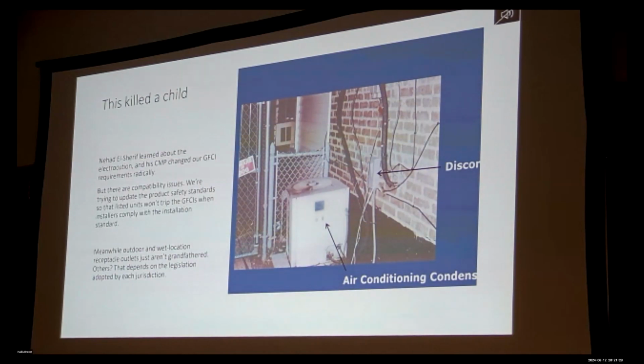GFCIs, and I sit on UL 943. GFCIs are required to pass certain tests, and the tests are to make sure that they'll trip real fast on a real small amount of current at 50 or 60 hertz. More and more motorized equipment is leaking other kinds of current because they have solid state controls, because it's Energy Star, because it's much cheaper to leak that current to ground than to shield.